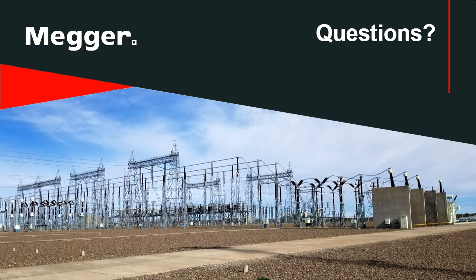or what standard you're abiding by, typically you'll go 50% from the highest reading. So if you had, let's say 100, 50, and 75, that 75 is within 50% of that 100, so that's fine. But that 50 micro ohms might be a little bit too low, right? So the other two might be too high, so you might have to do some cleaning or more operating of the breaker to get that contact resistance better.